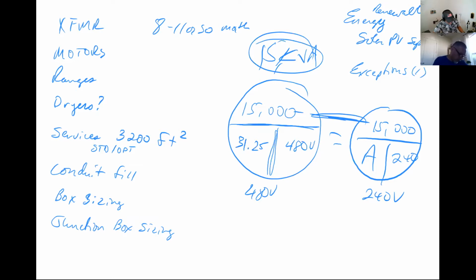So guess what I know without even doing anything else? I know that my secondary amperage is going to be 62.5, right? It doubles - if the other one halves, the other one doubles. So on 15,000 divided by 240 volt, that should give you a number that should be 62.5, provided your math was right.